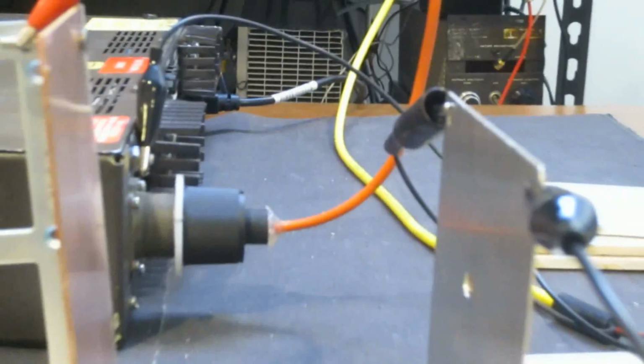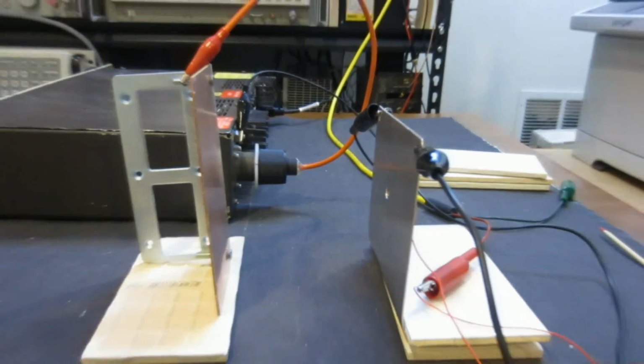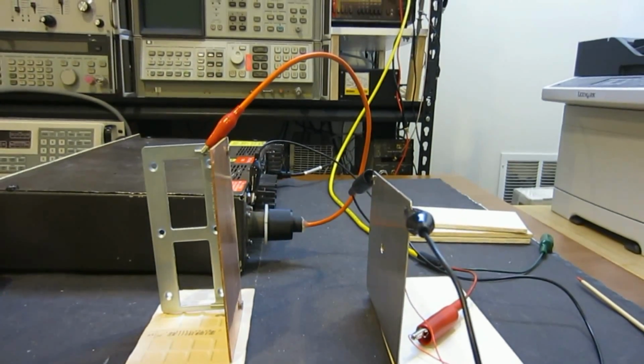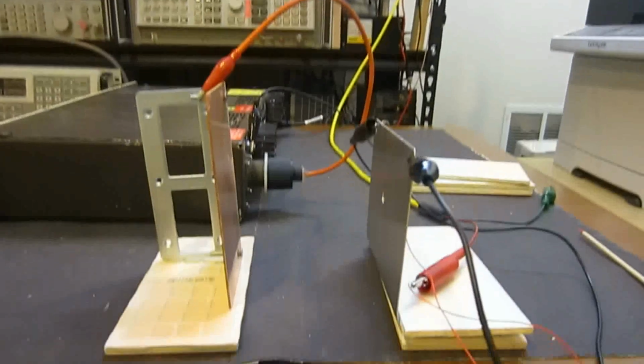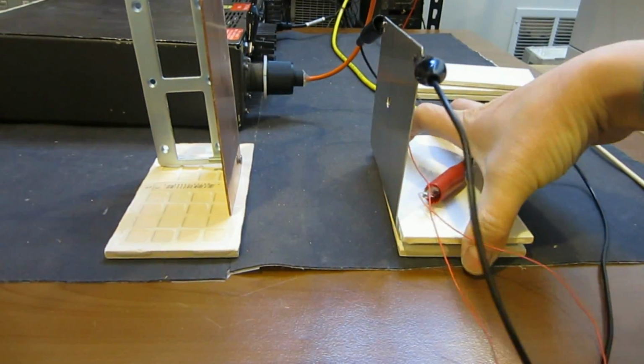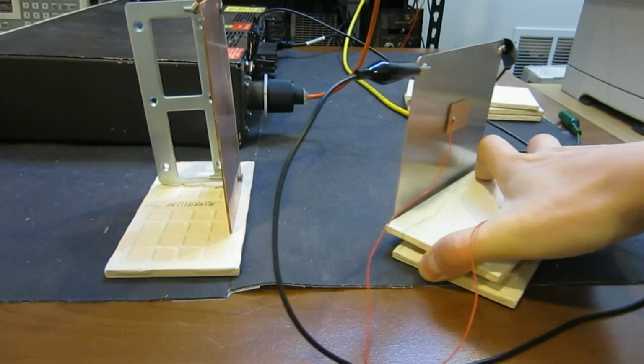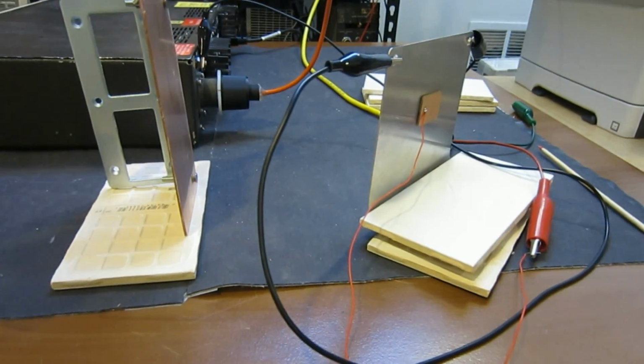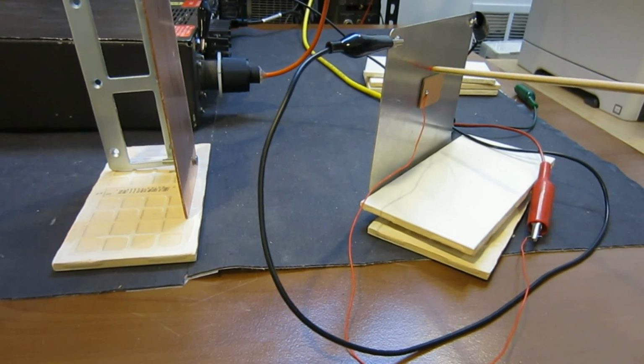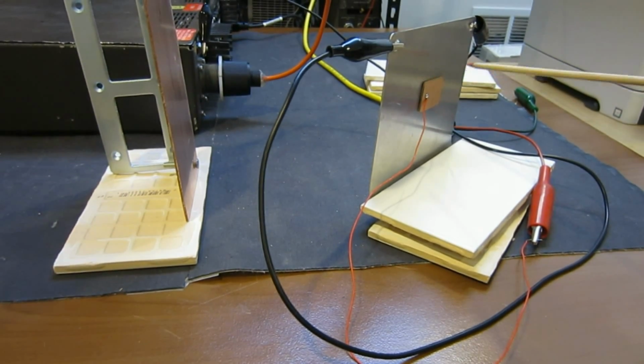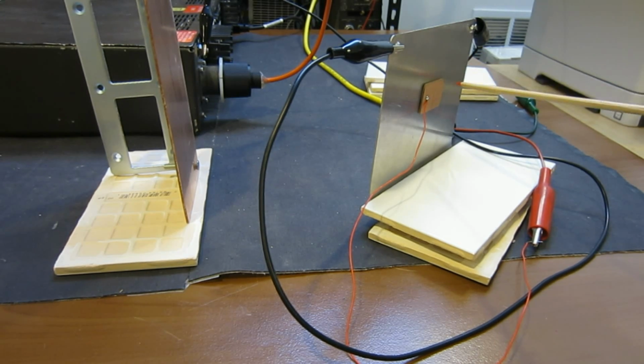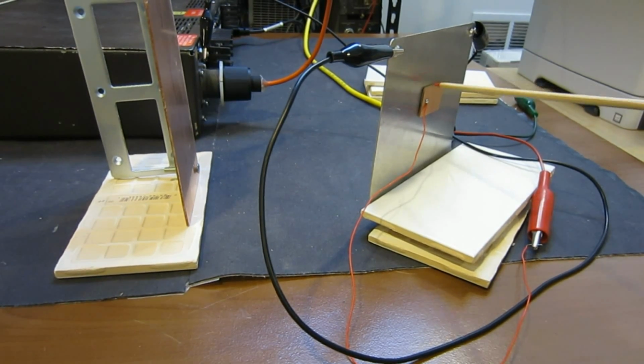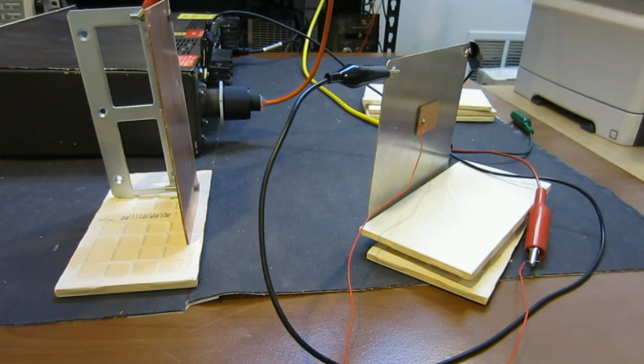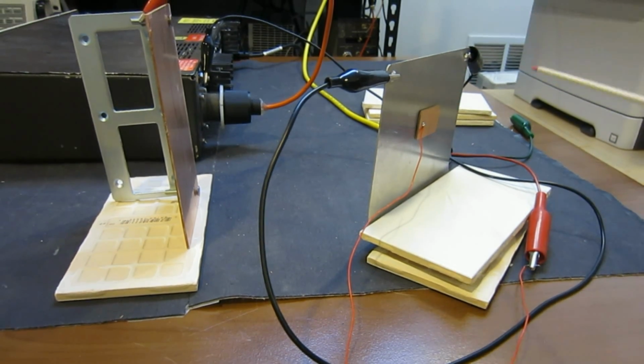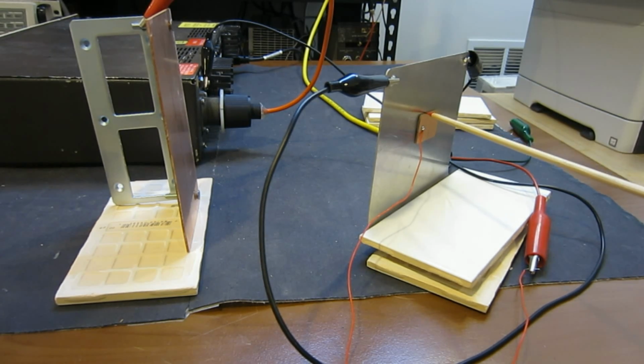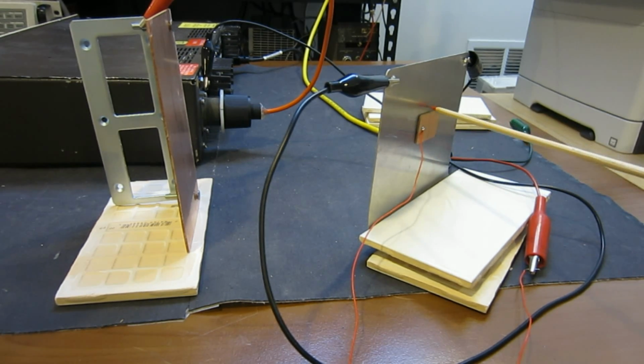Now, of course, as I explained before, to make that really useful, you have to have some kind of chopper stabilized amplifier, so that at each interval of the measurement, you know that you are starting from a known zero, so that you can calibrate against the theoretical value. Whereas right now, with this particular setup, you see the value drifts quite a bit because of the very high resistance input of the electrometer and our very small sensing element here.